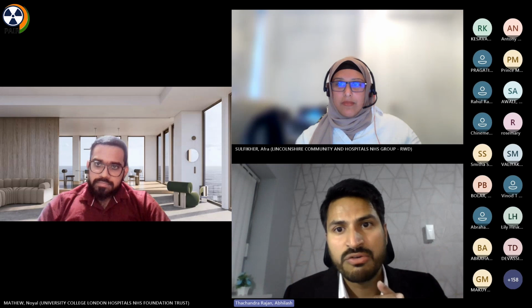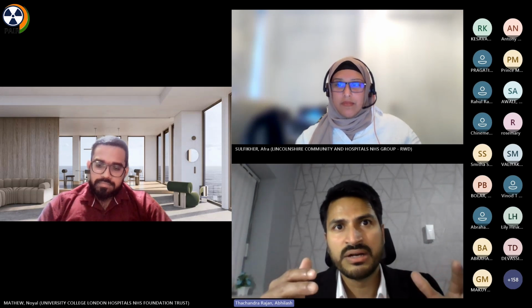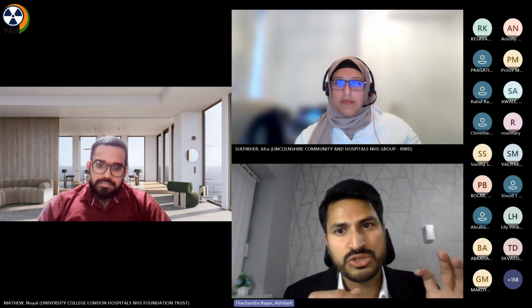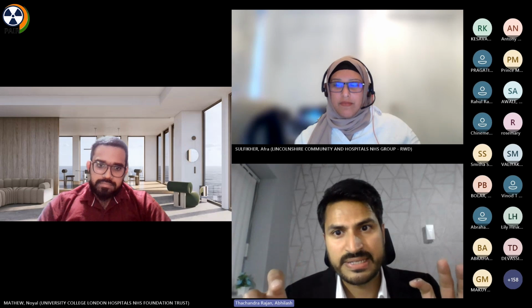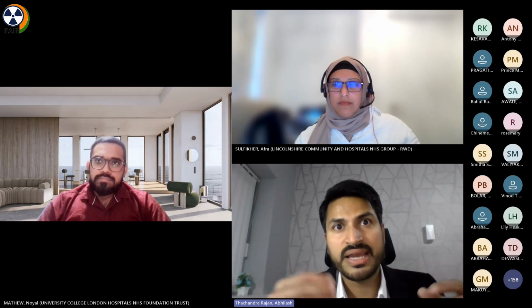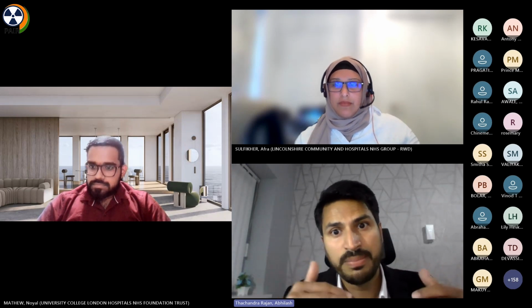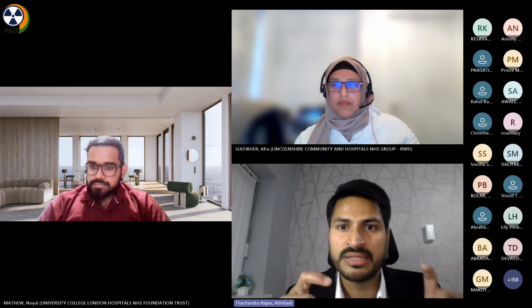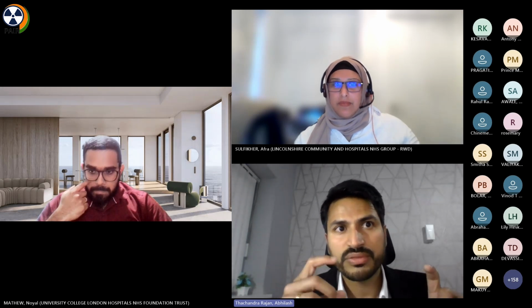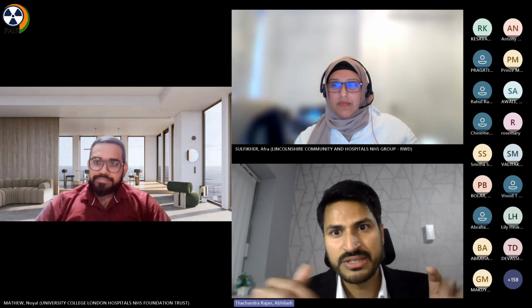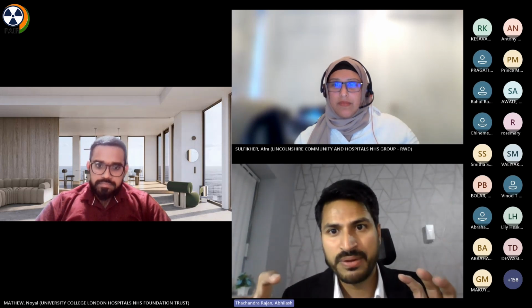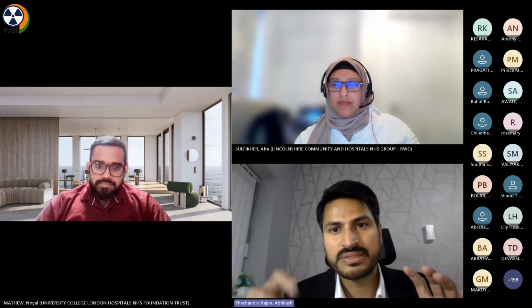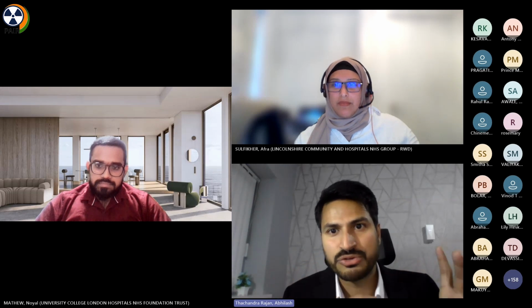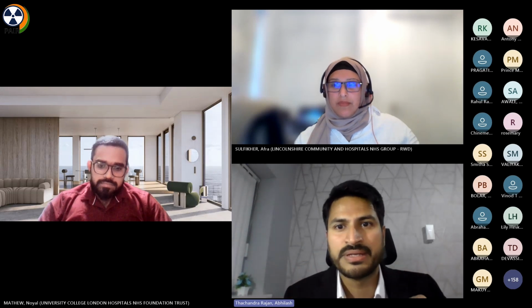So the length comes from the resonance frequency of each magnet. For a 3 Tesla, it's 128 resonance frequency, so its wavelength will be in the range of 25-ish. Half of that value is 12. That's meant for the 3 Tesla scanner. It can heat above and below 12, but maximum heating will be at that length. For a 1.5 Tesla, which is half of it, this 12 will become around 25. And for a 1 Tesla, which is 3 times the 3 Tesla length, it will be around 35-36 centimeters.